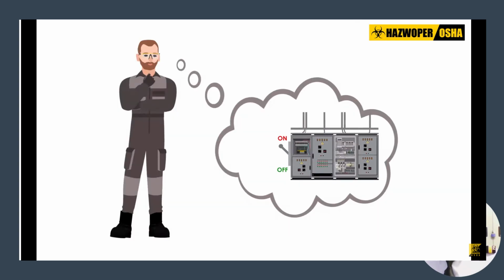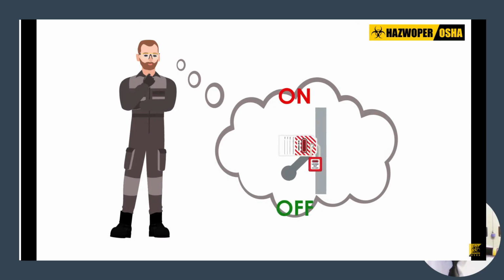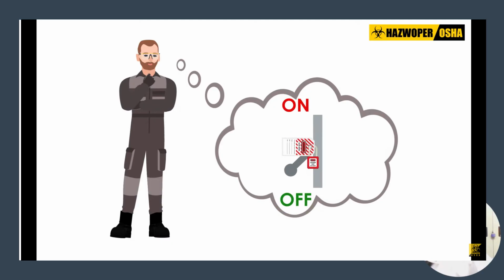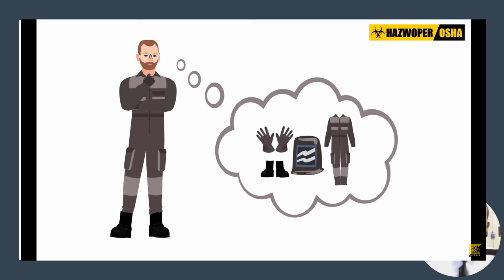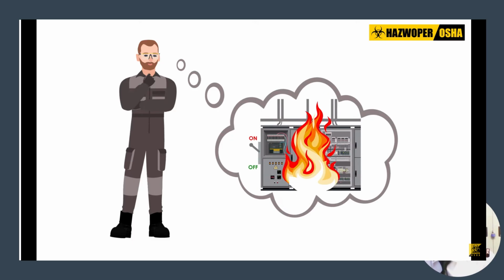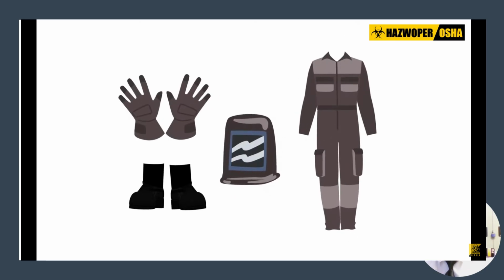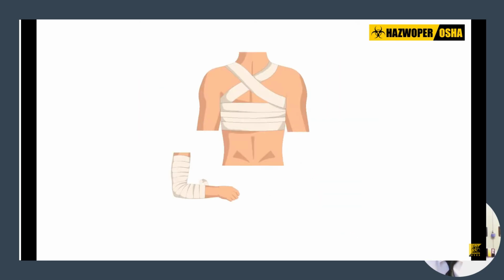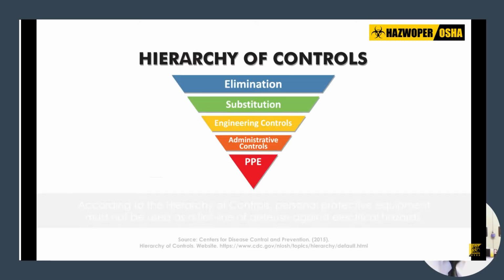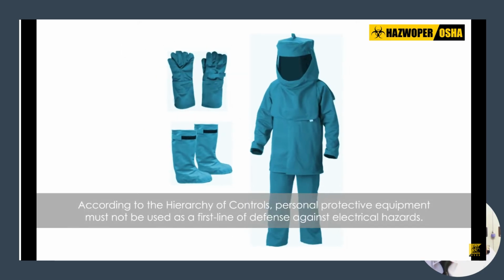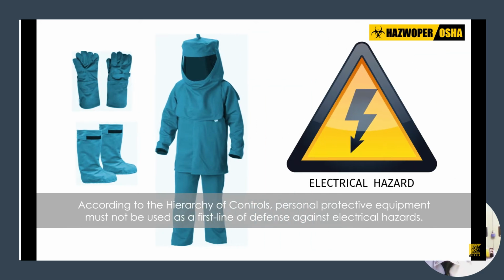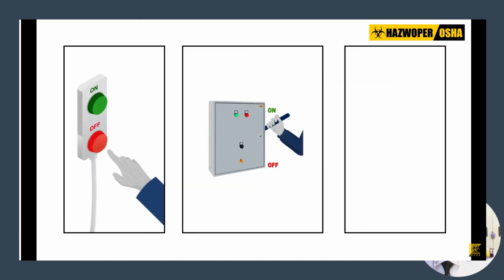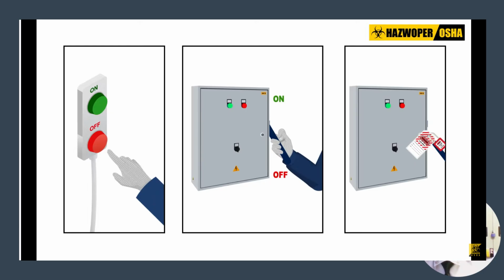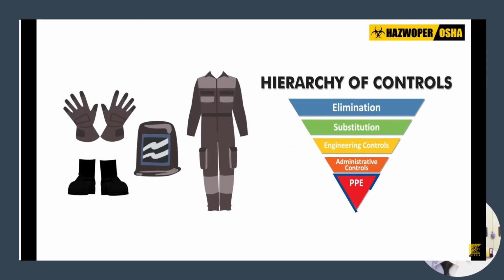The foreman's lack of training and understanding of electrical safety principles was evident from his belief that he could safely install circuit breaker boxes on the main distribution panel without de-energizing it, and that personal protective equipment would be enough to shield him from electric shock or arc flash. While the protective equipment and clothing did protect the foreman to some extent, he still suffered serious burns on a large portion of his body. According to the hierarchy of controls, personal protective equipment must not be used as a first line of defense against electrical hazards. Instead, de-energization of energy sources is the preferred approach, and personal protective equipment may be used as a last resort or may serve to provide additional protection.